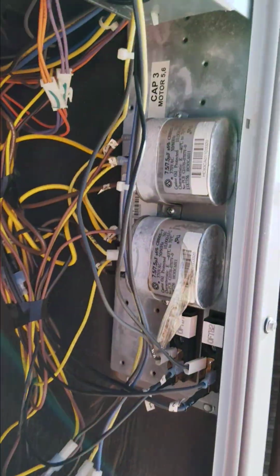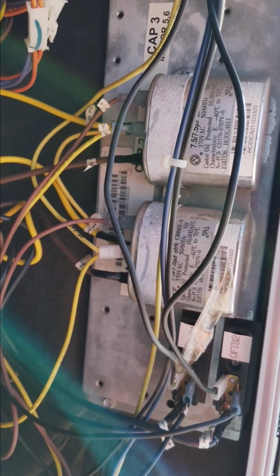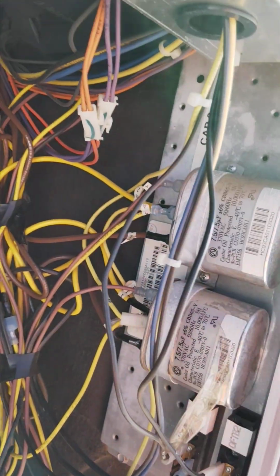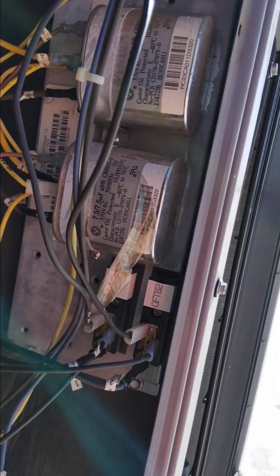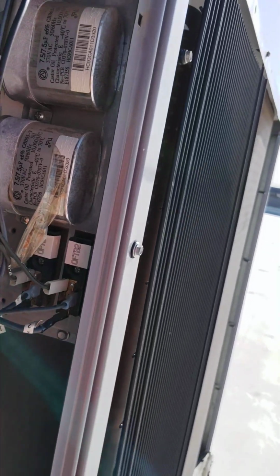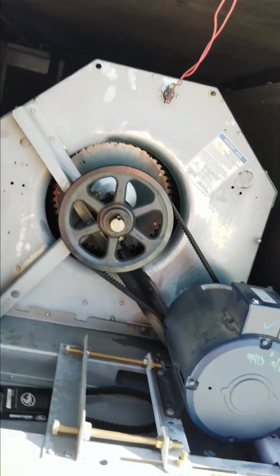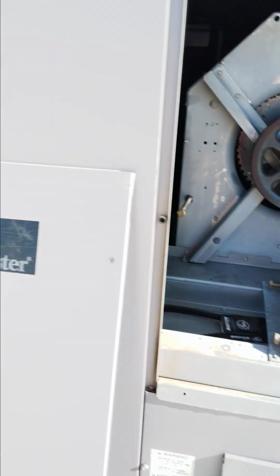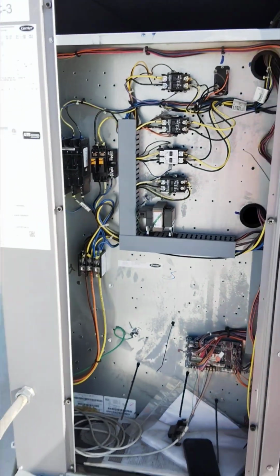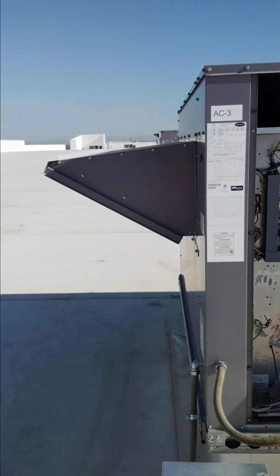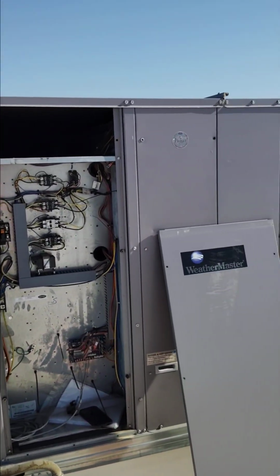There are some capacitors here, because those are single phase motors for the condenser. These are dual caps, so we need to check the capacitor and make sure they are still reading 7.5 microfarad, and verify the belt is good. If we need to change it, we change it. So that's a basic package unit that you do a PM on.